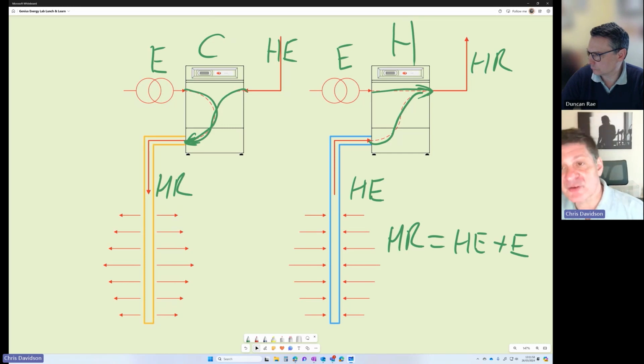So the processes of heating and cooling are not symmetrical from a ground source heat pump point of view, because the ratio of heat extracted, heat rejected, and electrical energy changes. That actually changes depending on the heat pump involved, largely coming down to the refrigerant gas, the type of heat exchanger, the compressor, controls, and so on.